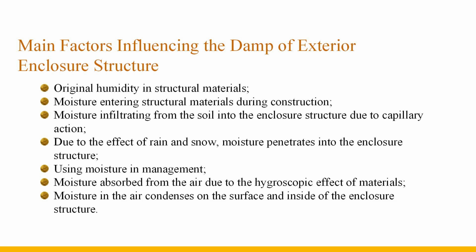Short-term or periodic moisture exposure can be improved after the weather improves or with ventilation, while long-term or sub-zero moisture exposure will reduce the structural strength and affect the durability of the building, reduce the thermal resistance of the envelope structure, and affect the building's thermal performance, breeding bacteria, affecting environmental hygiene. Therefore, the last one is the most harmful, and measures need to be taken to avoid it.